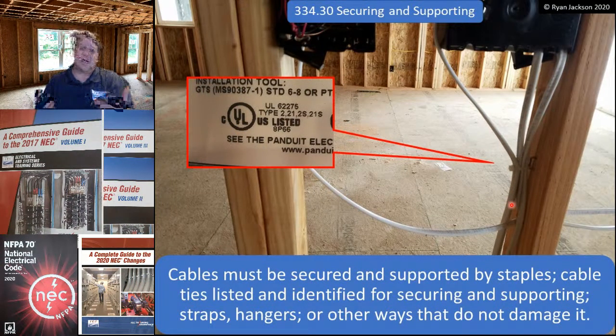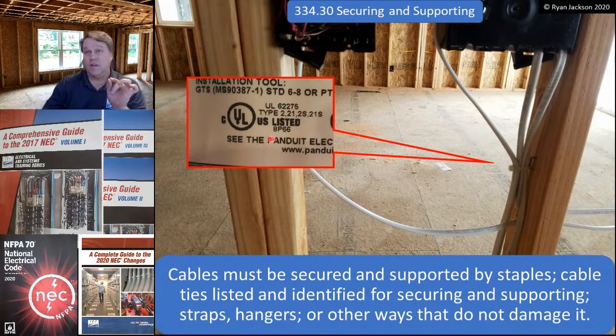You got to use the good cable ties for the wiring of a building. They have to be listed. That's requirement number one. And you can see in this zoom in here, this is a listed product. But it also has to be identified for securing and supporting, and that's a separate requirement. So it has to be listed, and it has to be identified for securing and supporting.